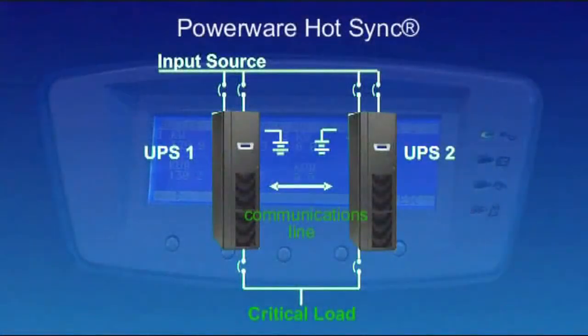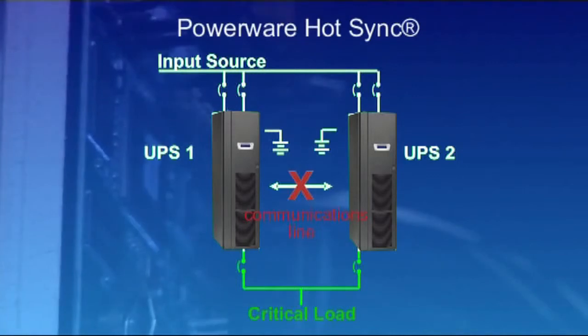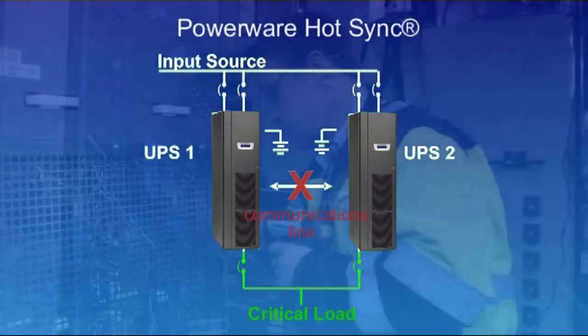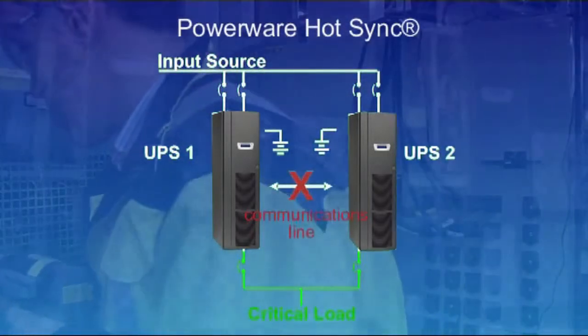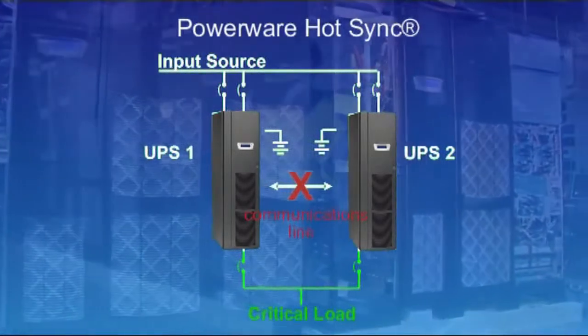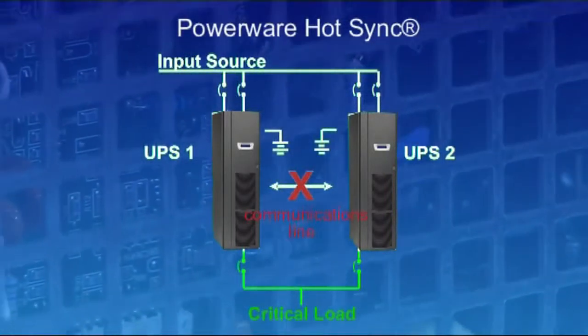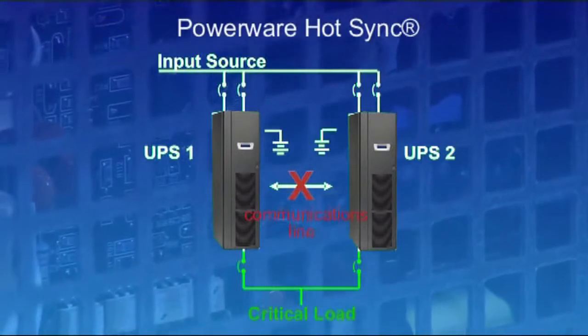Should a failure of any kind occur in a parallel HotSync configuration, the critical load still remains protected. This unique technology enables the UPS parallel system to operate without the need for any communication line between the UPSs or the external synchronization signal being transmitted to system modules. This eliminates the system level single point of failure.